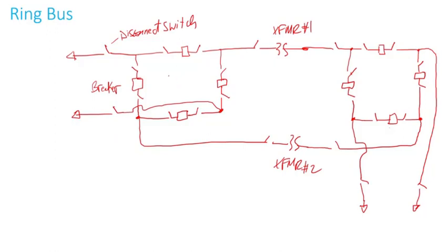This is a ring bus — it looks like a ring. You have four terminals: line one, line two, transformer one, and transformer two. Because you have four things connected, you need four breakers. Each breaker has one switch on its side for maintenance to isolate the breaker. In a separate video I talked about the trade-offs — straight bus versus ring bus versus breaker-and-a-half. Each one has trade-offs in terms of cost versus increased reliability.